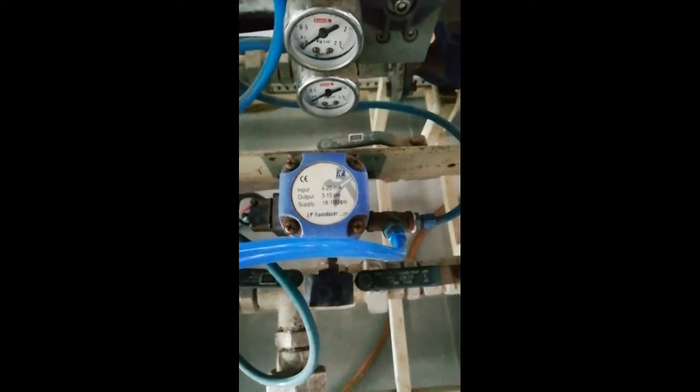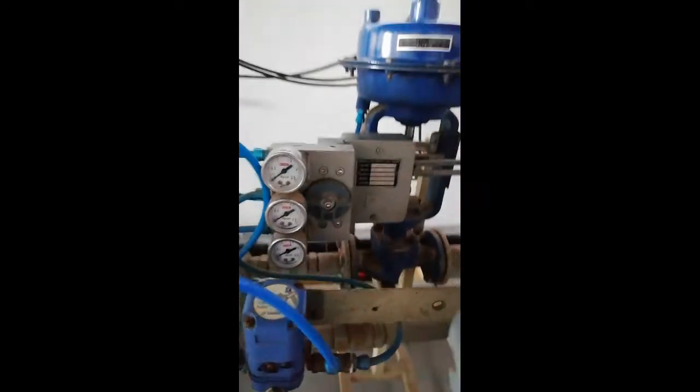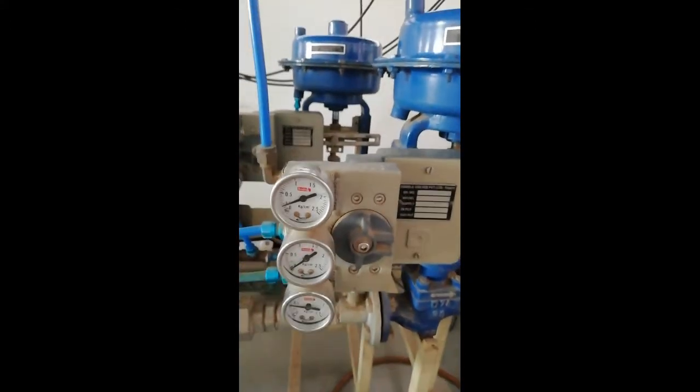There is one more important device: an I/P converter — a current-to-pressure converter — which is connected here. Since both of these are pneumatic valves, we need to convert the current signal into the appropriate pressure to operate these valves.